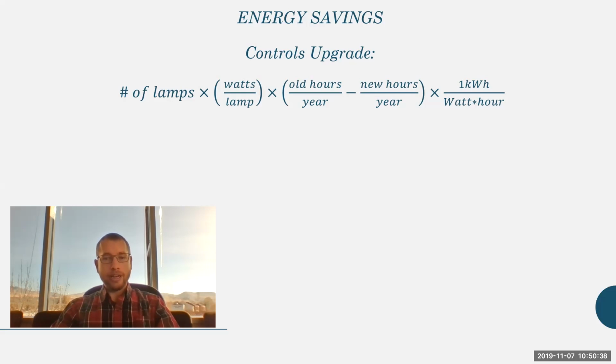So the lighting power density, all of those watts per square foot, are eventually coming out in terms of heat. And so that's adding to the internal load of the space, which has to be taken care of by the HVAC system. So if you do a huge upgrade and you convert all these 100-watt fixtures down to 10-watt fixtures, you're removing a whole bunch of heat sources from the space.